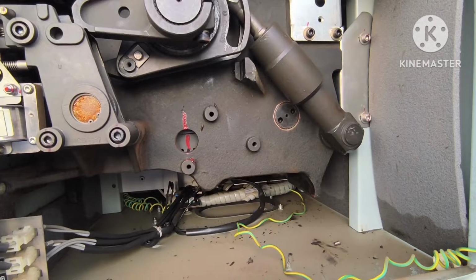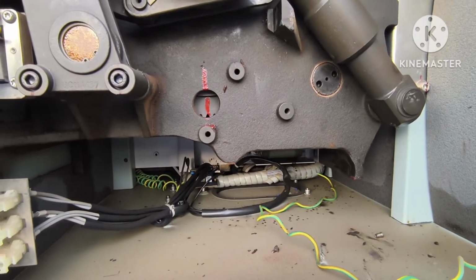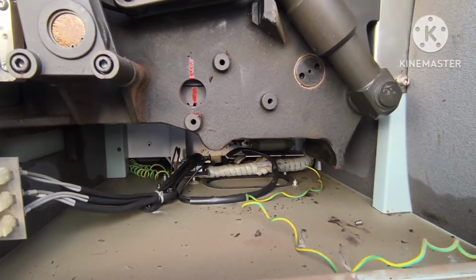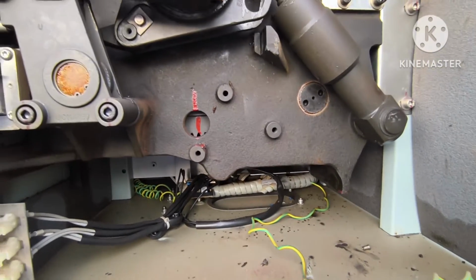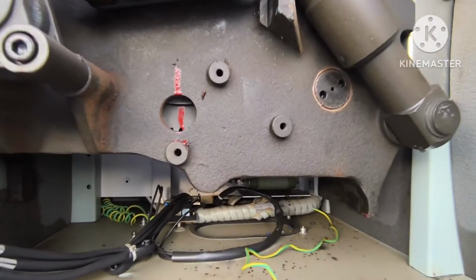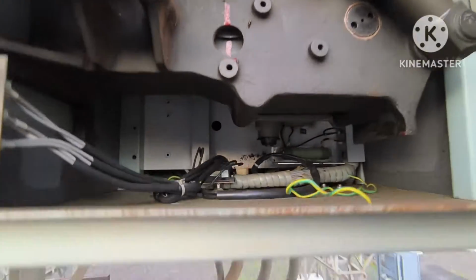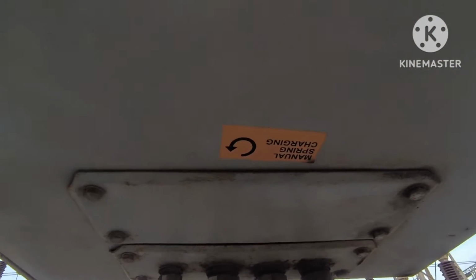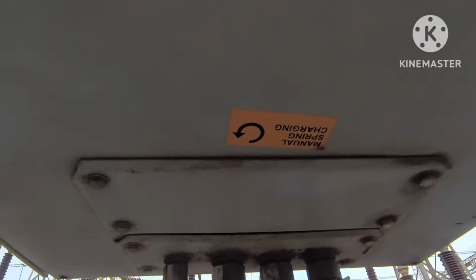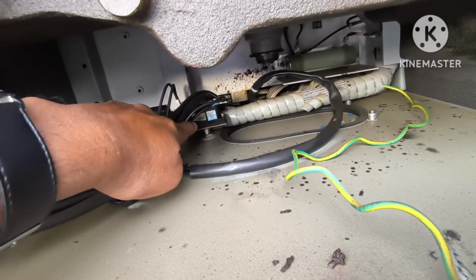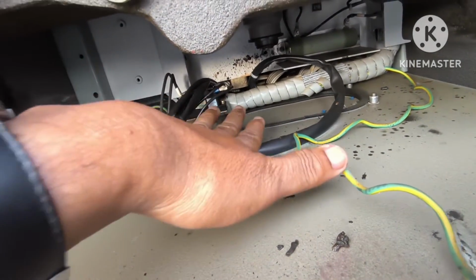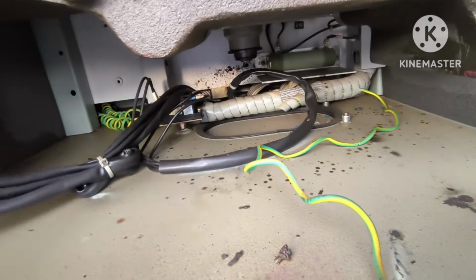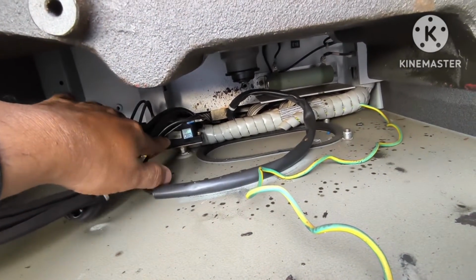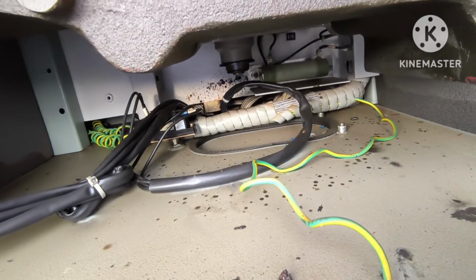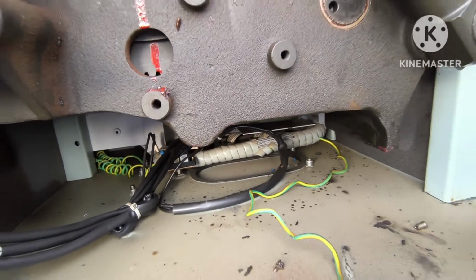In this type of breaker there is also a manual spring charging option. If the auxiliary supply has failed for a longer time, or there is a problem with the spring charging motor, then we can also charge the spring manually. Below this mechanism box one cover is there. We have to open this cover and insert the spring charging handle. While opening that plate, this limit switch will act. This will not allow the auxiliary supply to reach the motor. So while opening that plate, the supply to this motor will be disconnected. This is the work of this limit switch. So we can also charge the spring manually.